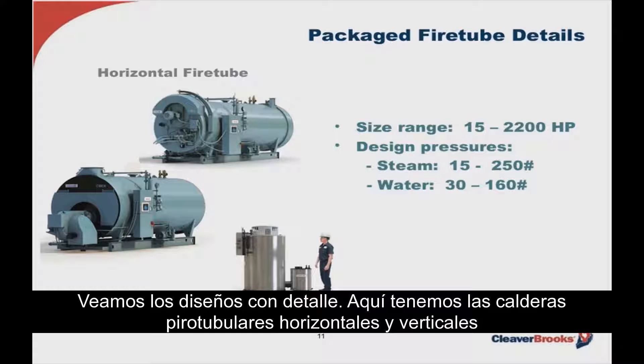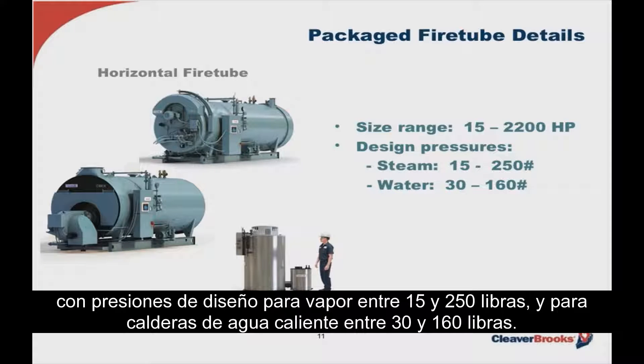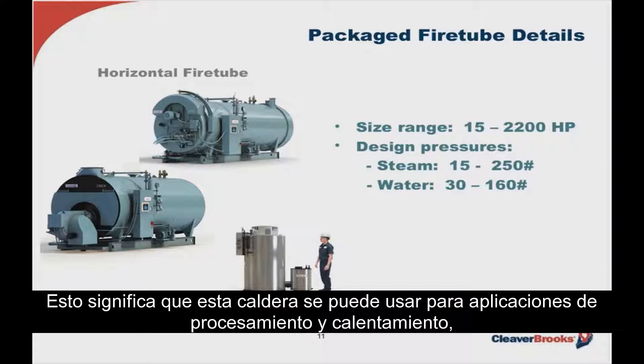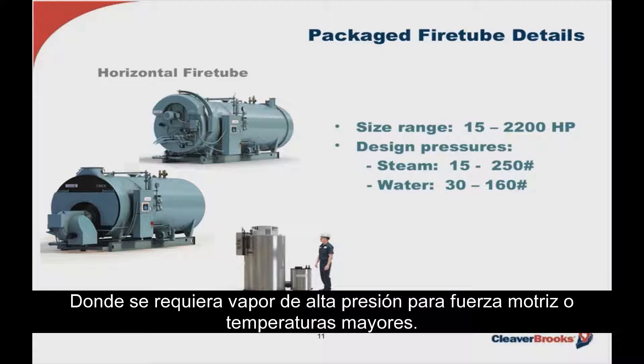Starting with the fire tube boiler, it comes in horizontal or vertical orientation and typically spans a package range between 15 and 2,200 horsepower, with design pressures for steam between 15 and 250 pounds and for hot water boilers between 30 and 160 pounds. This boiler can be used in both process and heating applications and is typically found in industrial process applications such as food, petrochemical plants, hospitals, university campuses, and wherever high-pressure steam is required for motive force or higher temperatures.